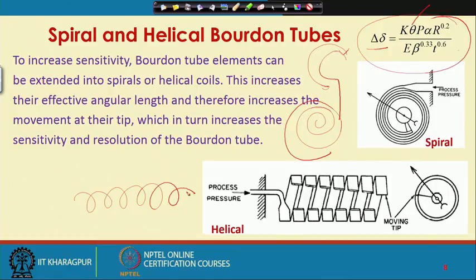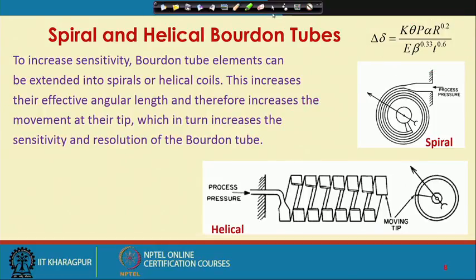Since with increase in length of the Bourdon tube, there will be more tip deflection for the same amount of pressure, the sensitivity of the Bourdon tube will increase. So, to increase sensitivity, Bourdon tube elements can be extended into spirals or helical coils. This increases their effective angular length and therefore increases the movement at their tip, which in turn increases the sensitivity and resolution of the Bourdon tube.